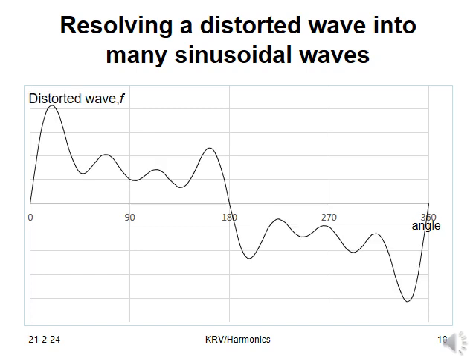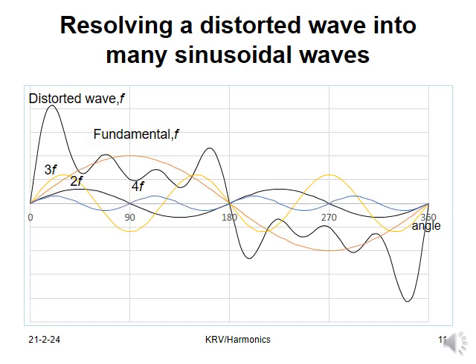How do we resolve a distorted wave into many sinusoidal waves? This distorted waveform, which is non-sinusoidal, has a frequency of f. This represents the load current drawn by the nonlinear load in a variable frequency drive. This is resolved into one fundamental with the same frequency f, another waveform with 2 times the frequency of f, yet another waveform with 3 times the frequency 3f, another waveform with 4 times the frequency, and so on. Theoretically, this resolution can go up to infinity, but for most practical purposes of measurement and mitigation, these are limited to either the 40th order or the 50th order.